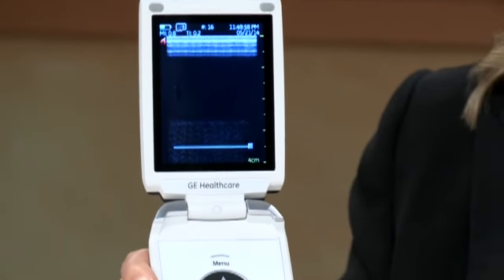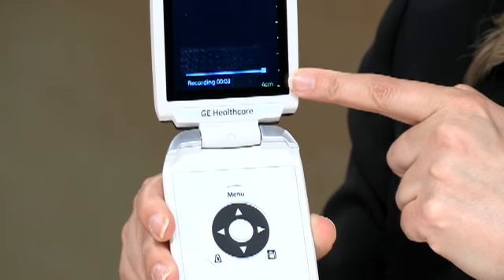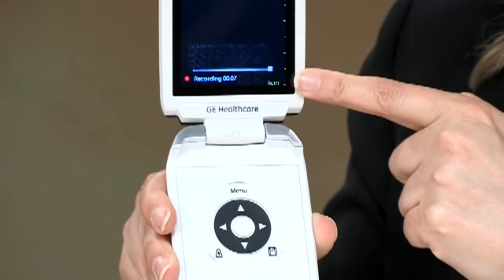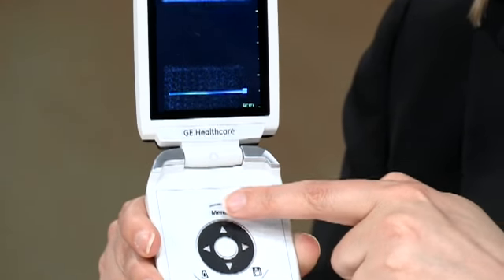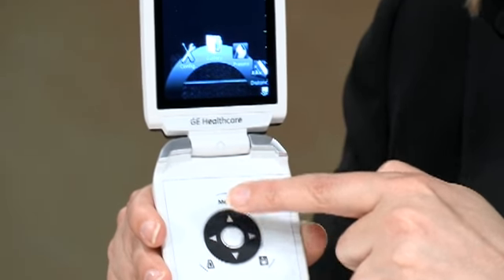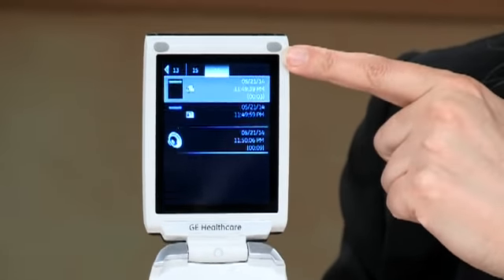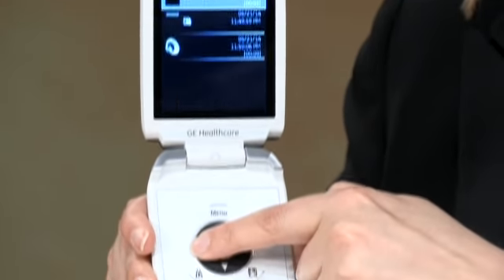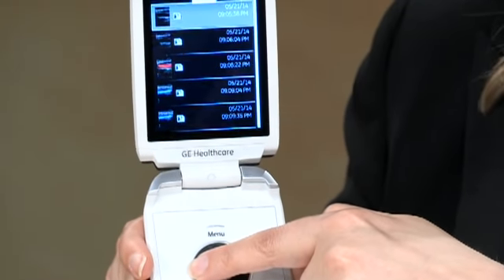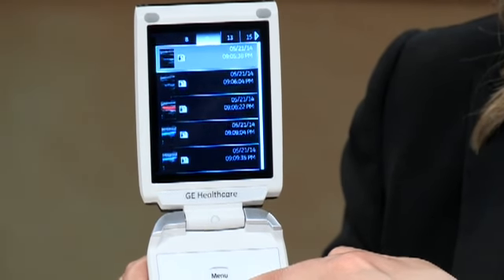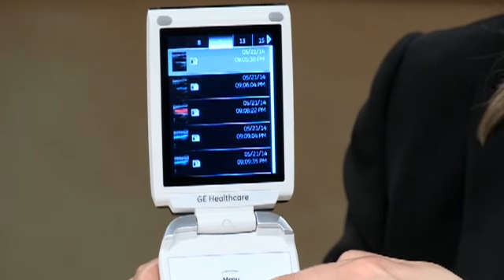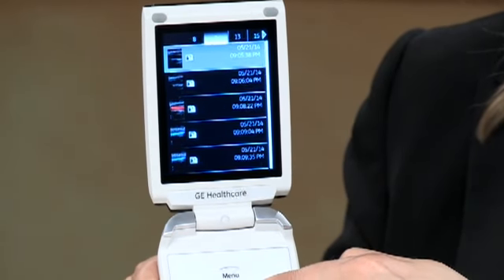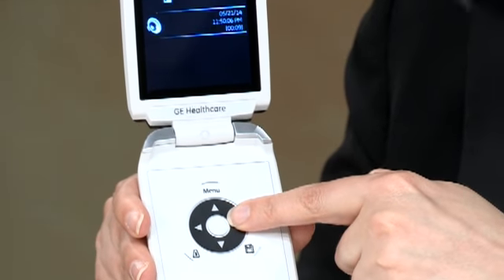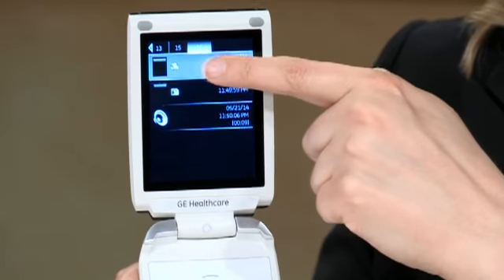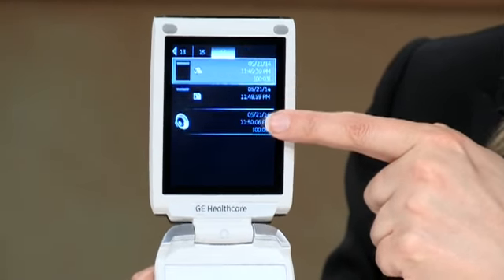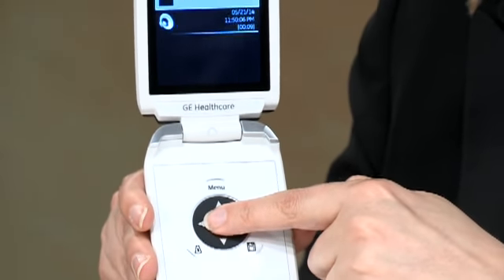To access the voice recording, press and hold the store key, and the icon will appear at the bottom of the screen indicating that a voice recording is being stored. Press any key to stop the recording. To access the gallery and where these files have been stored, press Menu and select Gallery. At the top of the screen, you will see the exam IDs that contain clinical information on the Vscan with dual probe device. Using the arrows, you can scroll these exams. An automation feature of the Vscan with dual probe device is that any exams that have been created that do not contain images will automatically be removed from the gallery so that you don't have to filter through empty exam IDs. Going back to the exam with which we just stored the images, you will see that we have the video displayed with the video icon, the still frame, and the voice recording. Using the navigation wheel, simply highlight the respective image that you wish to look at.